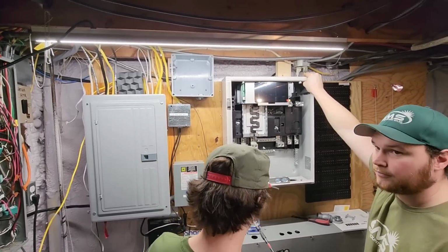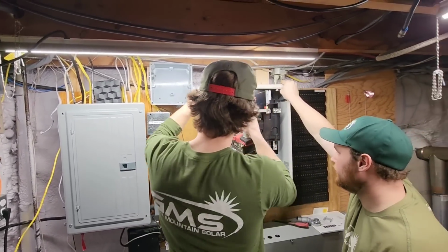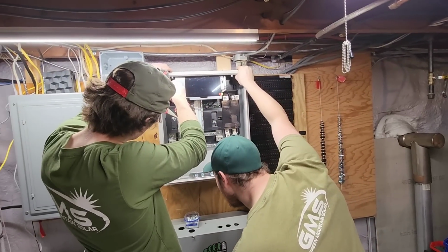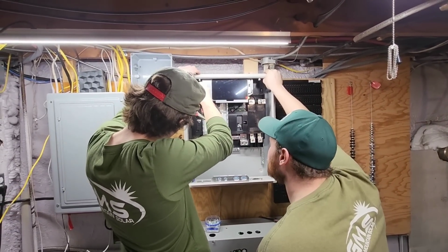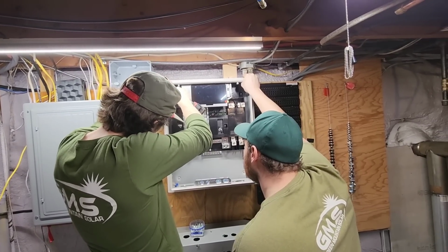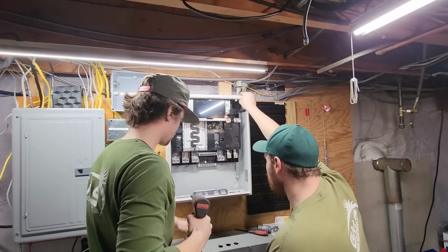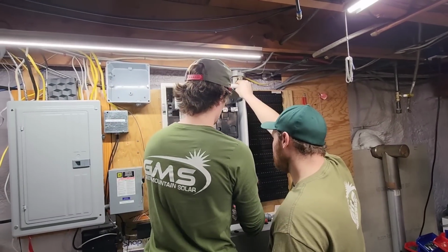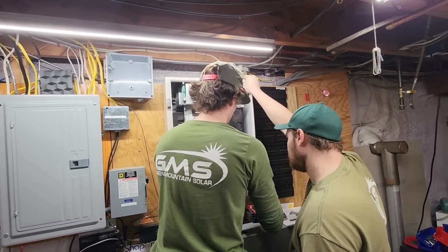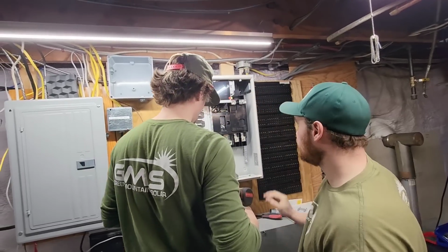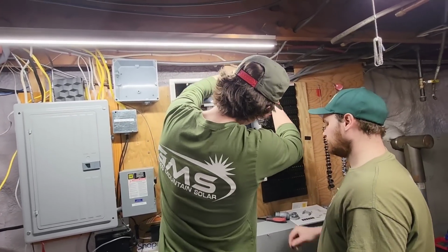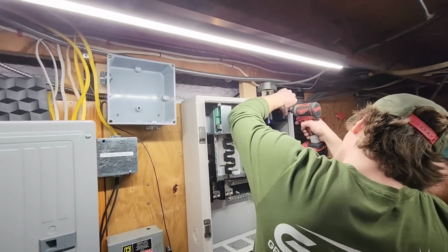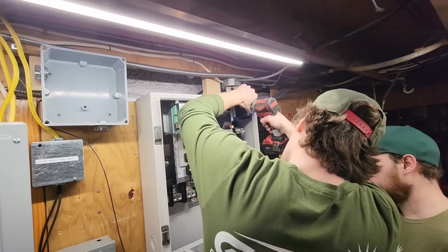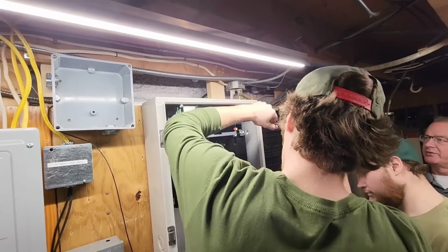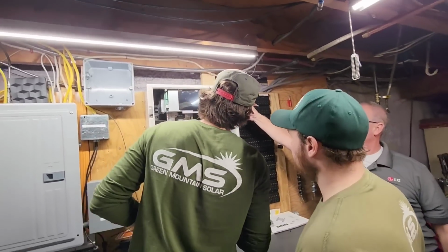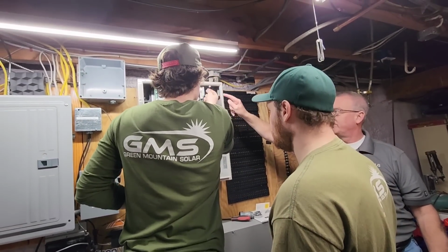You can see all the lugs on the bottom. On the bottom right is a non-backed up load. The lugs in the middle are grounds and neutrals. Bottom left is the backed up loads. This box is where the main service comes in, where the batteries come in, and where the solar can come in. You can also land the solar wherever it's already landed and just put a current transformer around it, as long as it's on the backed up load side of things. So it basically controls everything. It's also got a screen in the middle at the top where you can do the commissioning from, which we'll show you a little bit later.